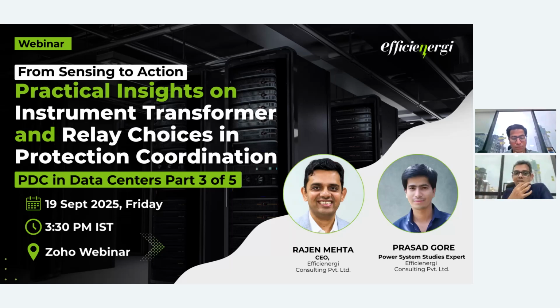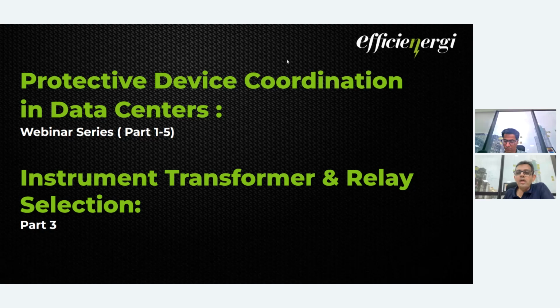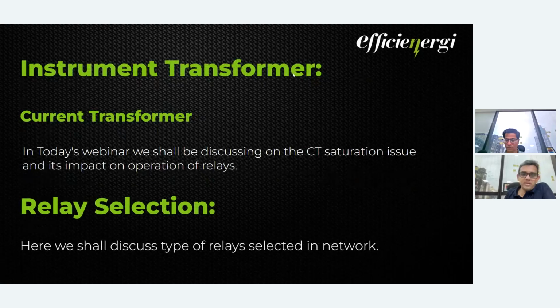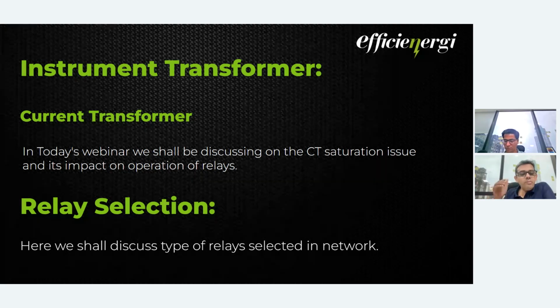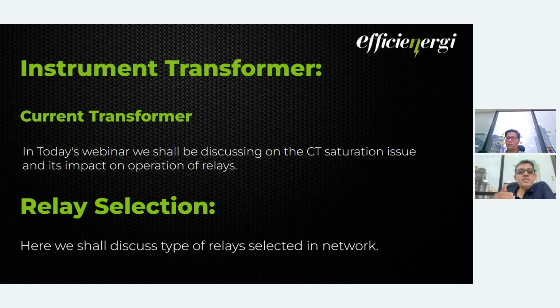So that is in some ways called a ghost tripping, where either it did not trip at all, or it tripped and you do not know the reason why it tripped. So one of the key areas here, which is today's topic that we are going to be taking on, is about instrument transformers and relay selections. And the first instrument transformer, which is most important for all of us to really dive into because they play a big role, is current transformers.